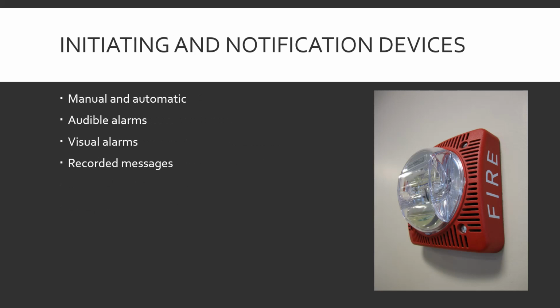Initiating and notification devices. There are manual and automatic, which is quite simply manual: someone's controlling it. That's the little pull station in the hallway, the little break glass and pull, whatever it may be. And automatic, that's the smoke detector, the rate of rise detector, all those fancy detectors that we'll get to in a little while.